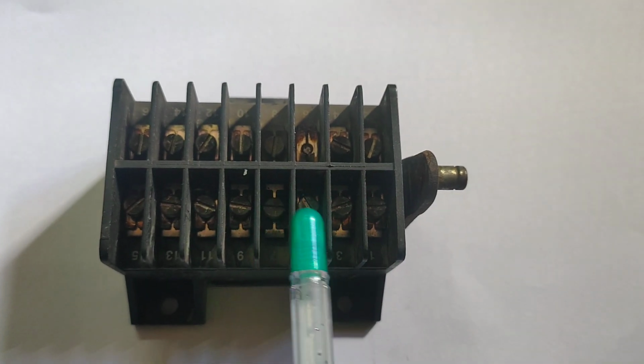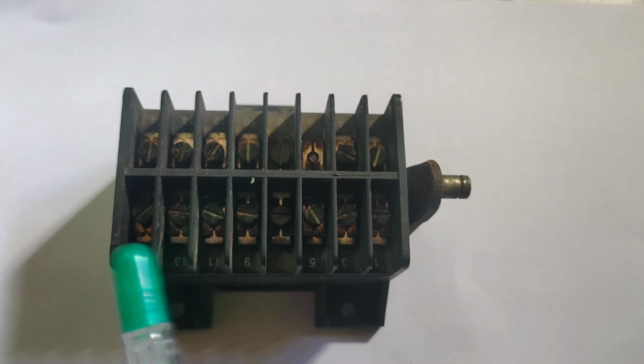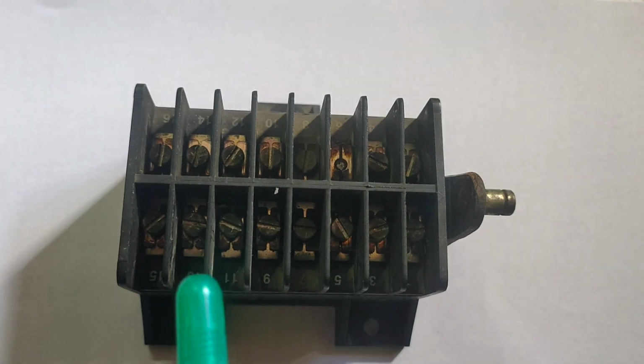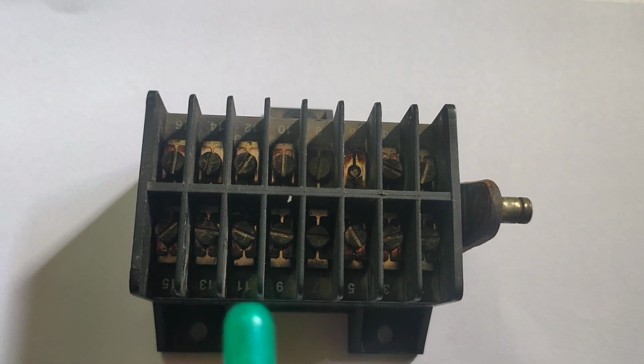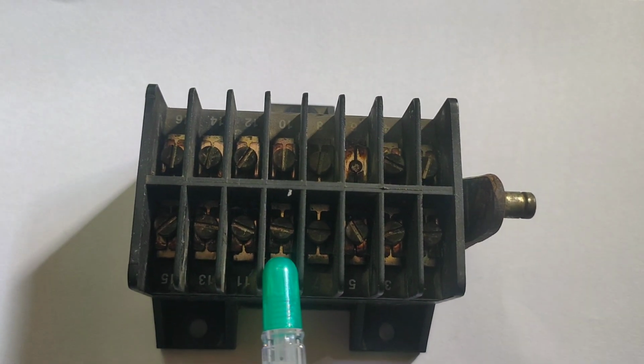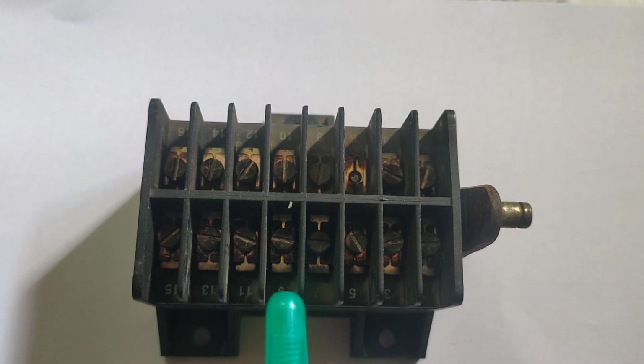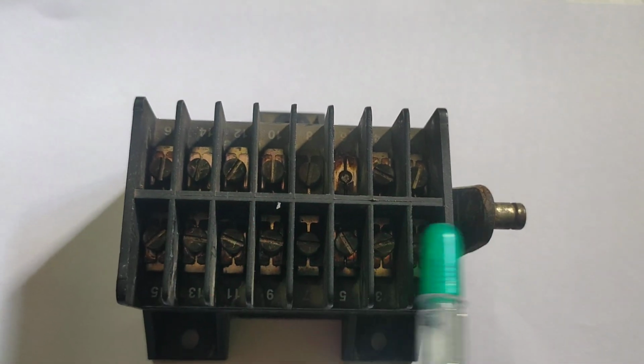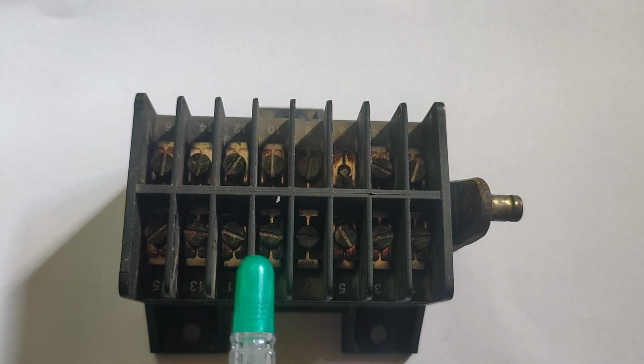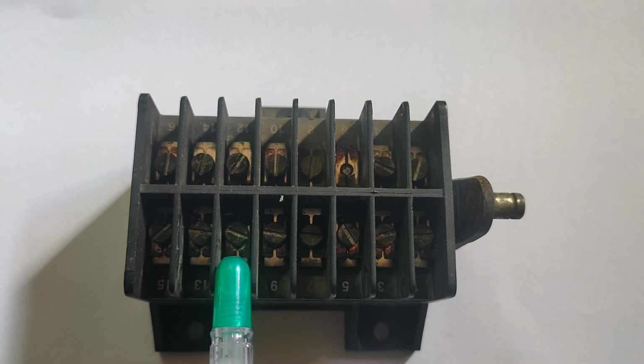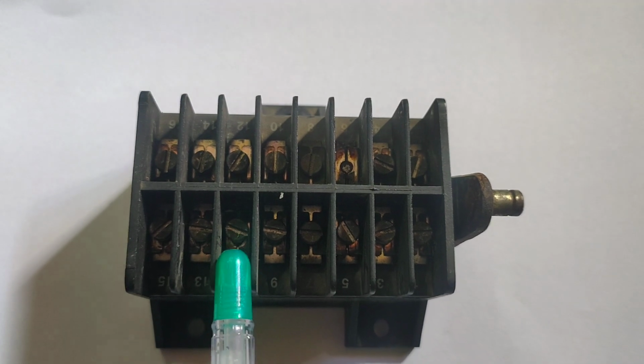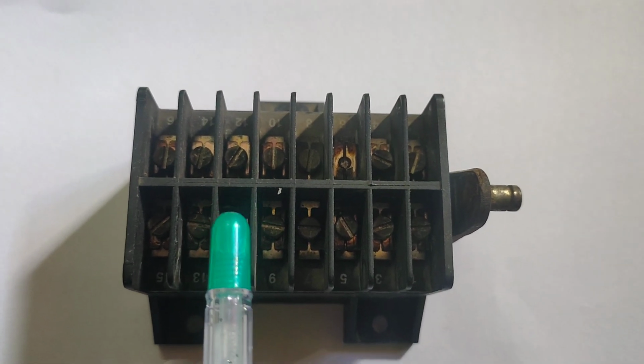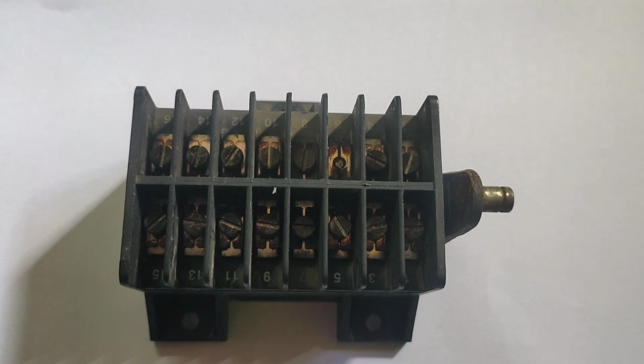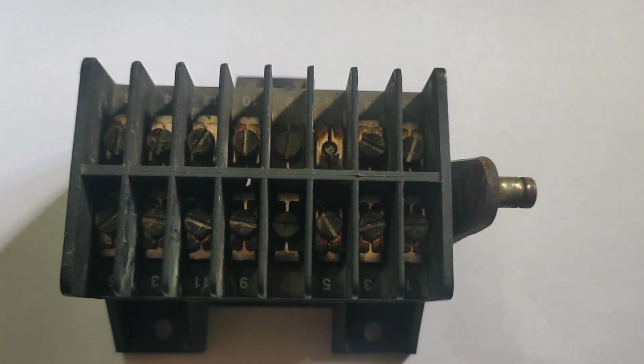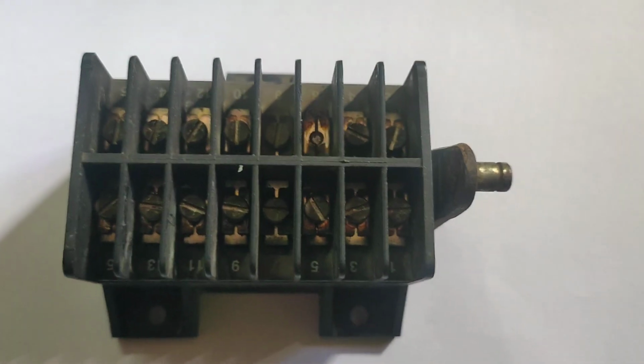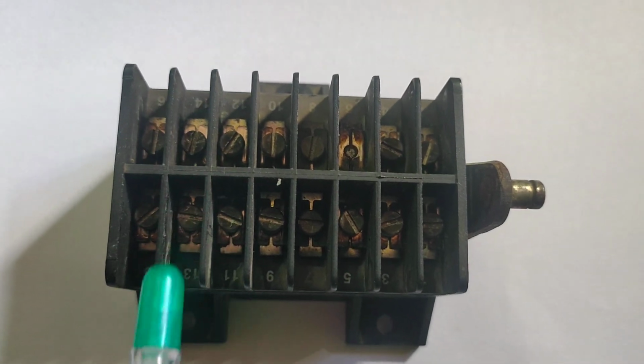SF6 alarm, trip, lockout contact - all the paths inside the control circuit, you can see the S1 NO or S1 NC contact. These 4 NO and 4 NC contacts inside the circuit breaker are used for providing the proper response to the proper control circuit path.